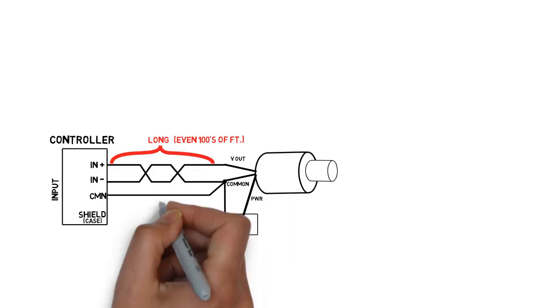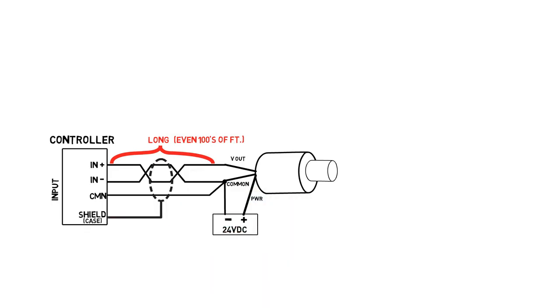Connect the cable shield to the shield connection, which should go to protective earth ground. Usually, the shield should be connected on only one end. If the shield is already connected at the sensor, don't connect it at the controller.